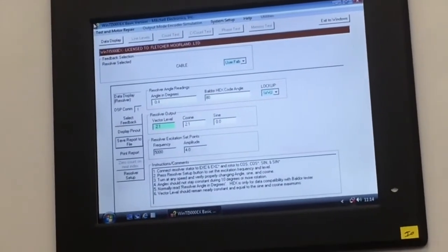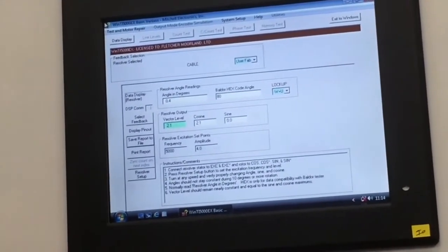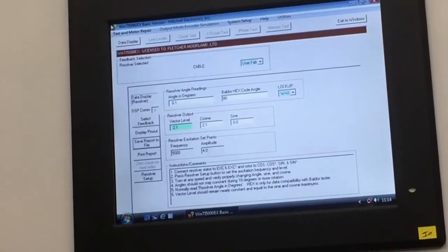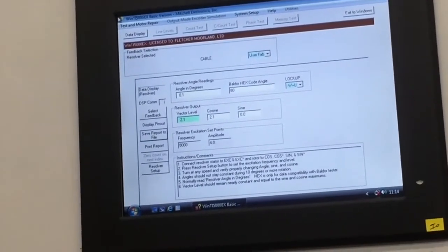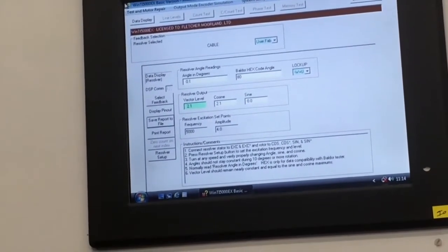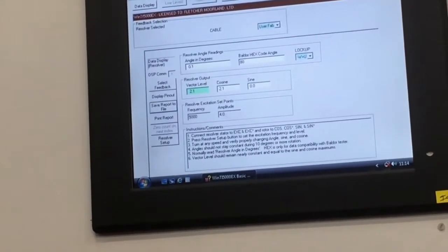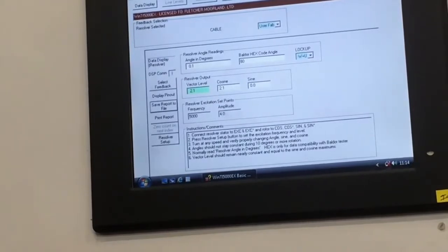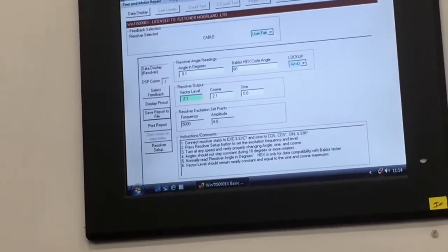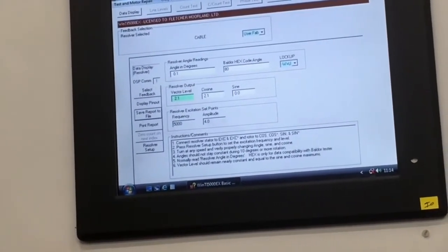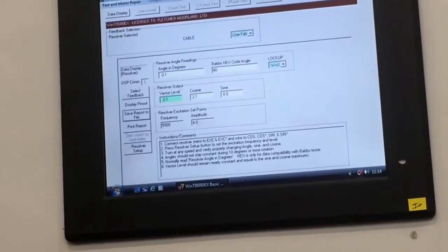The software position here is now showing zero angle degrees and we can also see that the vector level for this motor has now been corrected by putting a new resolver in. And once we are happy with this, we will do a few revolutions to make sure everything is correct. We are getting the right angle, we are getting the right voltage amplitude out, and then we will set the drive together with the motor and perform the load test.